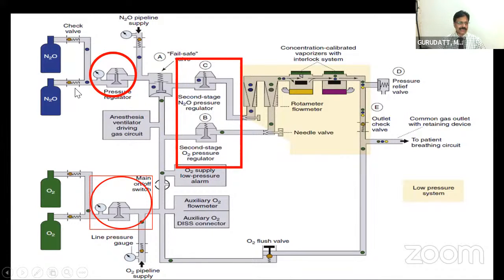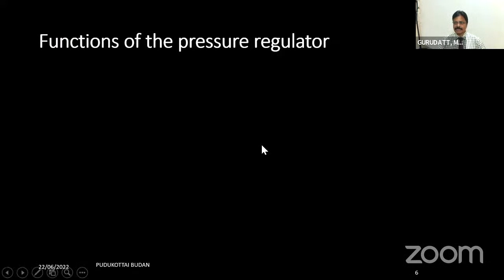These primary pressure regulators convert the high pressure of the cylinders, 750 psig of nitrous oxide and 2000 psig of oxygen, to 45 psig that enters into the intermediate pressure system. One question commonly asked is, what are the functions of a pressure regulator, or why does a pressure regulator have to be there? Just imagine that there are no pressure regulators. That means you have opened the oxygen and nitrous oxide cylinders, and that high pressure gas is flowing directly into the anesthesia machine. You have set a flow of say 3 or 4 liters of oxygen. Just imagine that there are no pressure regulators between the cylinders and the flow meters. I have set a flow of about 3 or 4 liters. And what will happen after say 5 or 10 minutes?